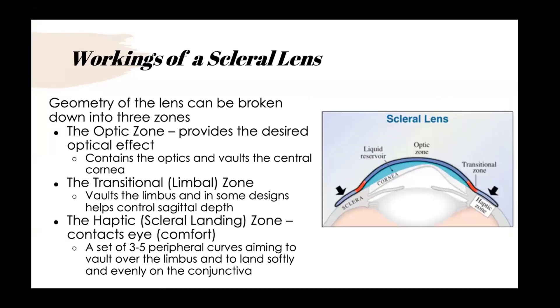Moving on to scleral lens basics: scleral lenses have a tear reservoir, vault over the cornea and the limbus, and align the edges nicely with the conjunctiva. We break the lens into three major zones: the optic zone, which is the central zone providing the optical effect and vaulting over the central cornea; the transitional zone toward the limbus, which can help control sagittal depth and limbal clearance; and the haptic or scleral landing zone, which involves several peripheral curves aiming to vault over the limbus and land softly and evenly on the conjunctiva.